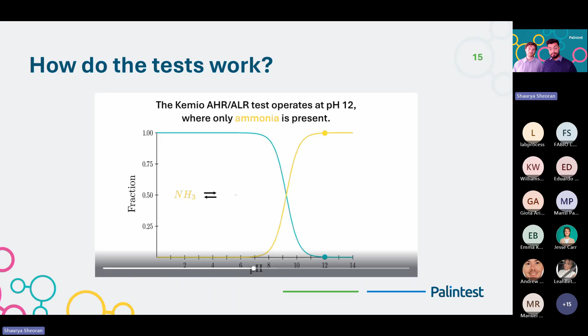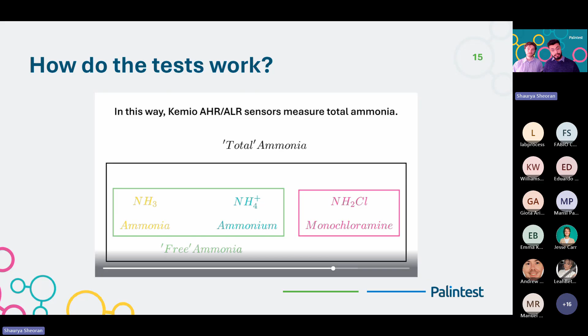So what our sensor does is it will first react with chlorine, the nitrogen reacts with chlorine, and then it would convert everything into monochloramine. And that's how we are able to measure both. We are able to measure the nitrogen that is already combined with chlorine and the nitrogen that is free. And together it's consisting of total ammonia. So here's the relationship between the 3 different species and how they operate. Our Kemio, when you do the test step, you will see all the 3 results, all the 3 measurements.